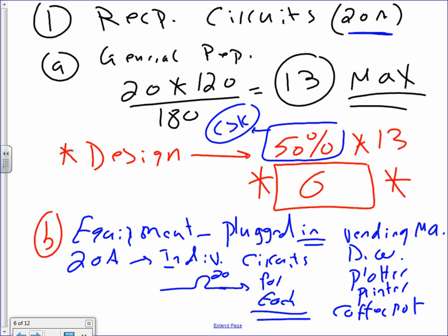Now, can I put the coffee pot and the printer on one 20 amp circuit? I bet if you do the math on it, you can. Not a good idea. Remember, we are designers. Good design. Can I have a thumbs up, Chad, on where we came up with individual circuits for the equipment? Now, when we start circuiting, and you start throwing the receptacles and you see a plotter, how am I going to circuit this receptacle for the plotter, Chad? Individual circuit. Pick it up, put it on a 20 amp circuit, move on. Okay? All right, any question about these receptacles? Let's go to the next.